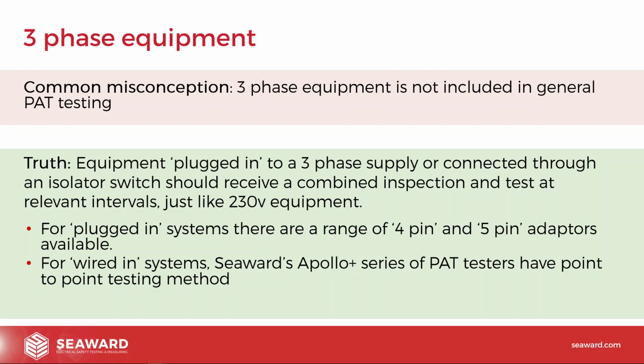We also do three-phase leakage adapters. So if you want to do the live leakage tests for the 250, 250 plus and the Apollos, we've got an external leakage adapter that you can connect into the mains. You connect the three-phase equipment into it, and then it will carry out leakage tests on that. If you want to do mains leakage tests, obviously you can't power three-phase equipment from the PAT testers because they only generate single-phase voltages. But we do a three-phase leakage adapter that allows you to do that extra level of tests on that equipment as well.